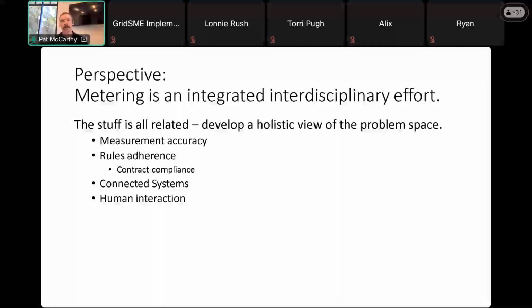But what the story is really about is the interconnectedness of the metering. This project had 3 different points of metering, all set up completely differently for different purposes. They had a CAISO revenue meter, I think 69 kV, which might tell you what utility it lived in if you're nuanced. They also had an HMI operator view of the plant's output, and a generator control governor type control system. These were all on different current transformers, with different devices driving measurement values into the subsequent systems.